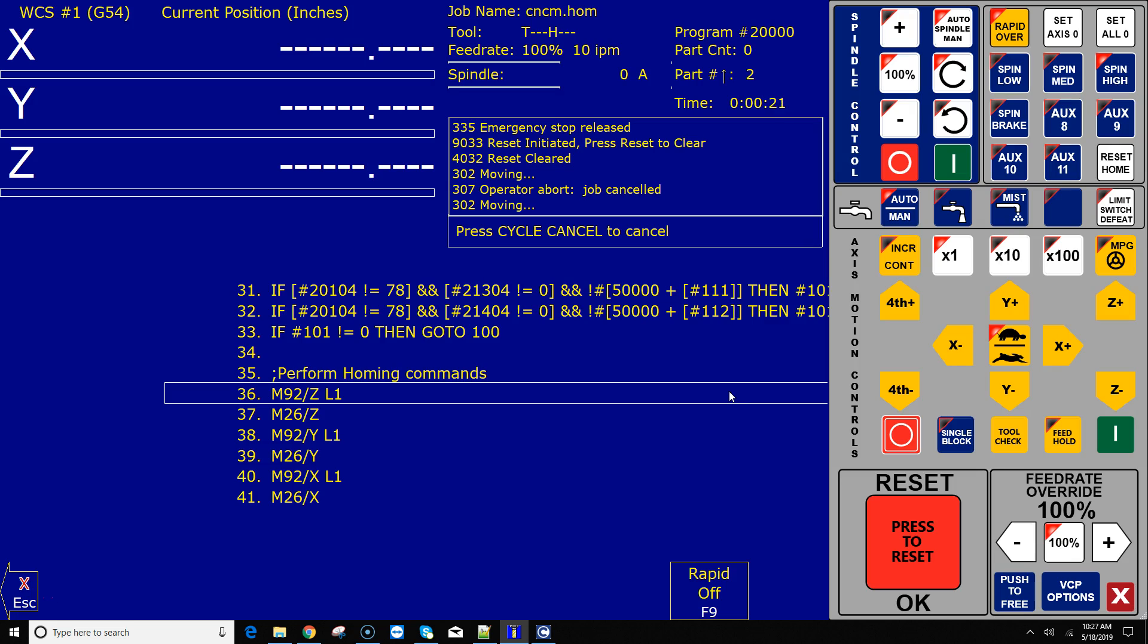That M code, if you are backing off the switch and it notices that the machine moves more than a quarter of an inch, that M code thinks 'Hey, there is something wrong. If I hit a switch and I have to move more than a quarter of an inch to clear it, that switch is probably broken, the wire is broken, the switch isn't working very well, something's sticky, something's wrong.' So it shuts down at that point to give you an opportunity to fix the problem.